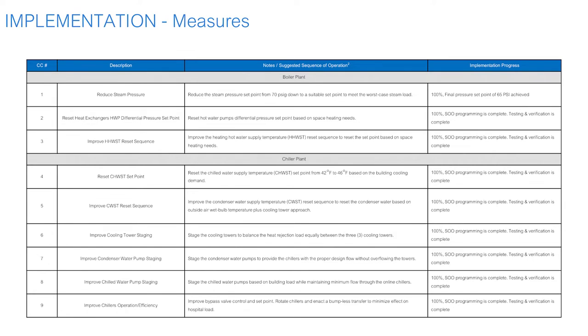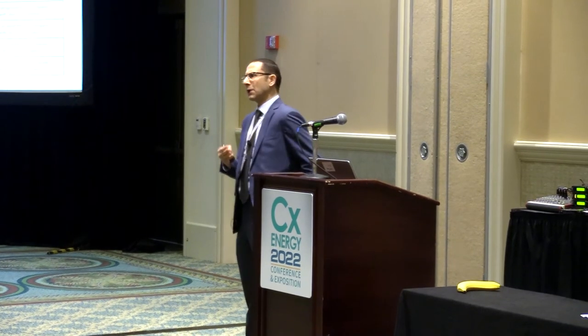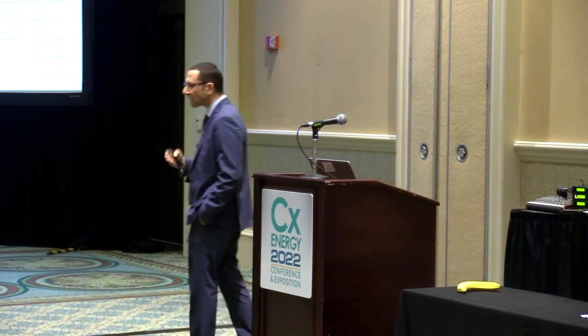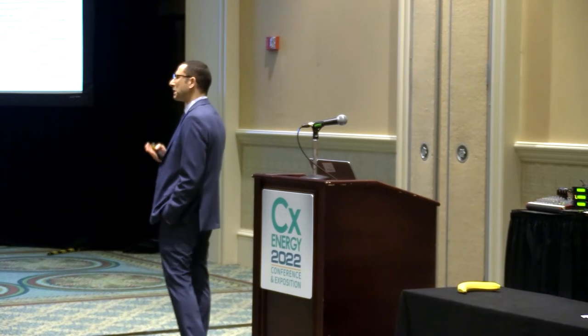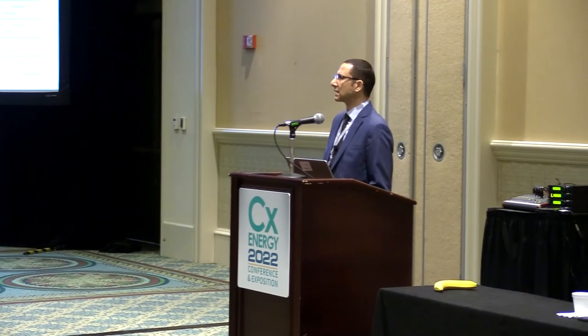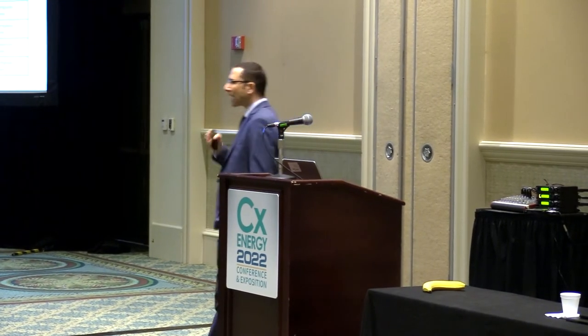Reset is extremely important, as this has been the message throughout this week, right? Reset for differential pressure, reset for discharge temperature, reset for return duct humidity. There are so many things that happen in a building, especially in a hospital or critical environment, that there are a lot of opportunities people miss because it's not that easy. It's easier to say, I'm going to just run things at 100% because I'm guaranteed I'm not going to have a humidity issue, I'm not going to have grills that sweat, right?